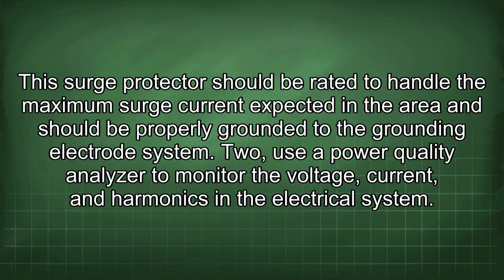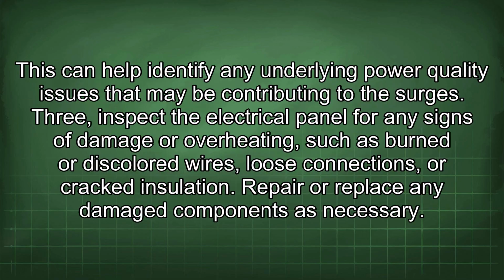2. Use a power quality analyzer to monitor the voltage, current, and harmonics in the electrical system. This can help identify any underlying power quality issues that may be contributing to the surges. 3. Inspect the electrical panel for any signs of damage or overheating, such as burned or discolored wires, loose connections, or cracked insulation. Repair or replace any damaged components as necessary.